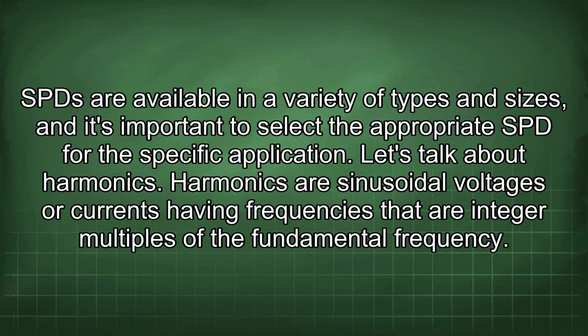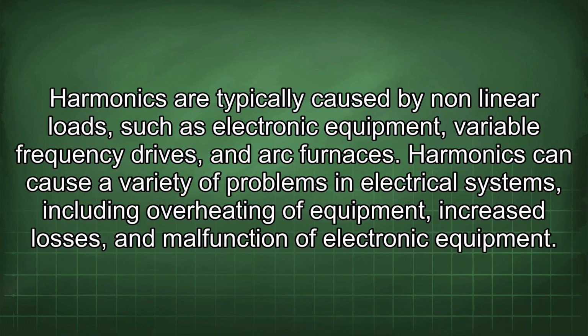Harmonics are sinusoidal voltages or currents having frequencies that are integer multiples of the fundamental frequency. Harmonics are typically caused by nonlinear loads such as electronic equipment, variable frequency drives, and arc furnaces.